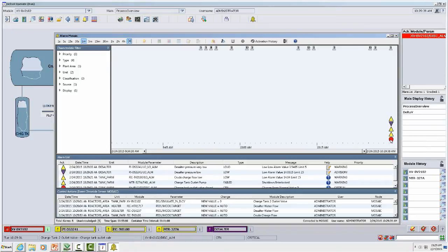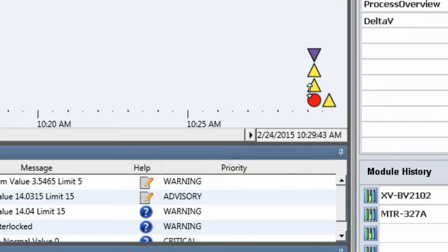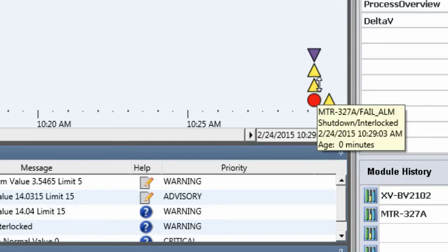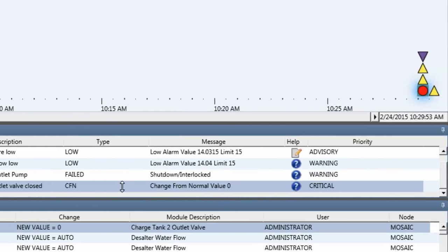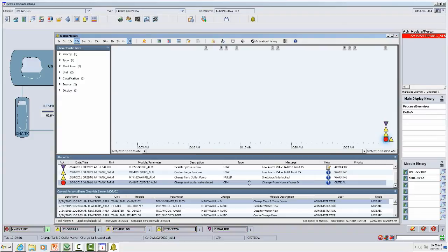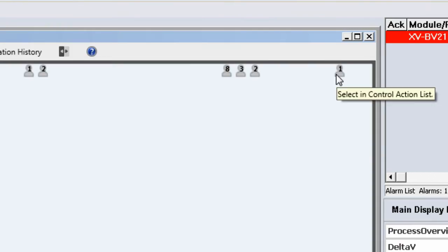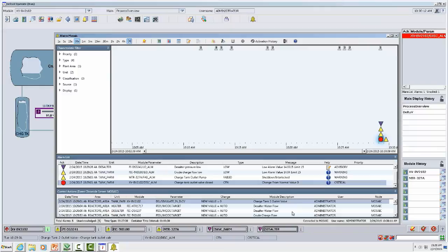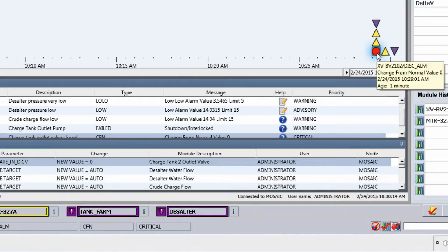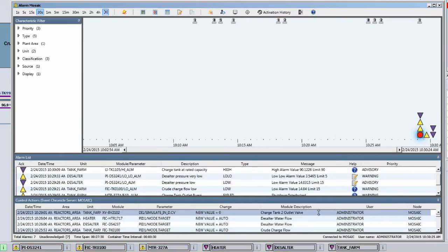Now you see that stacking and unstacking action. When you mouse hover over the alarms you get some information about them, and if you highlight one you get a corresponding highlighting in the alarm list of all the details relative to that alarm. At the top there are icons — these little heads with numbers on them — representing control actions taken in the same time segment. When you highlight an alarm it identifies any control actions and picks out the one that occurred just before the alarm flood. In this case, looking at the control action, we see that somebody closed a block valve.